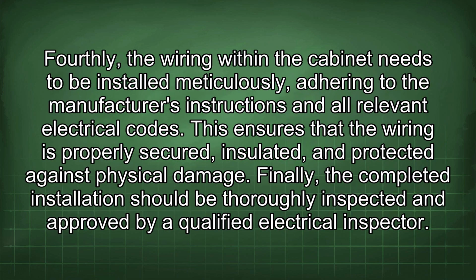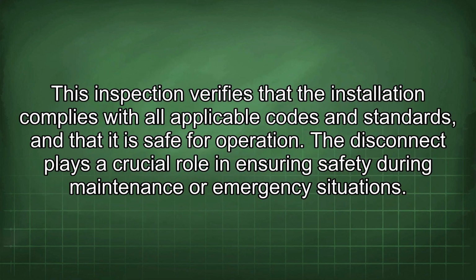Fourthly, the wiring within the cabinet needs to be installed meticulously, adhering to the manufacturer's instructions and all relevant electrical codes. This ensures that the wiring is properly secured, insulated, and protected against physical damage. Finally, the completed installation should be thoroughly inspected and approved by a qualified electrical inspector. This inspection verifies that the installation complies with all applicable codes and standards, and that it is safe for operation.